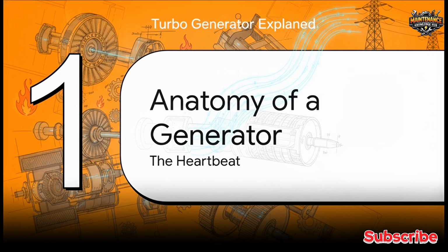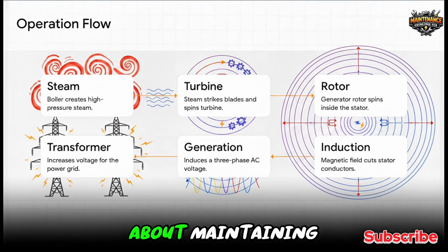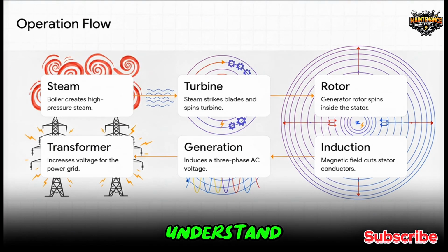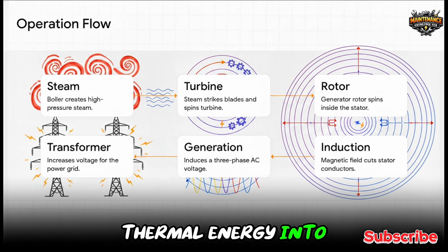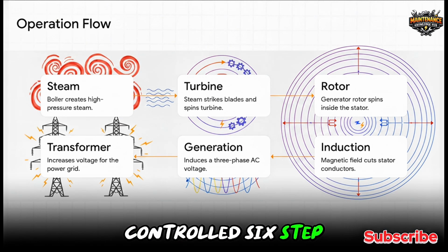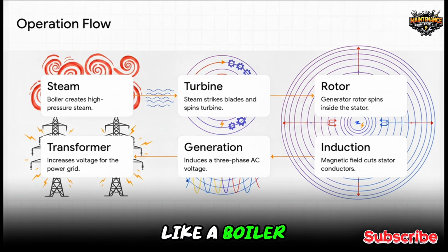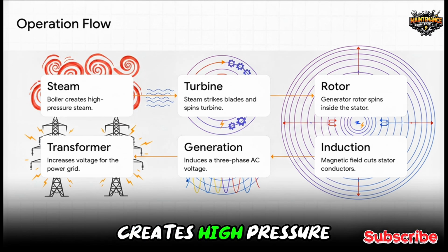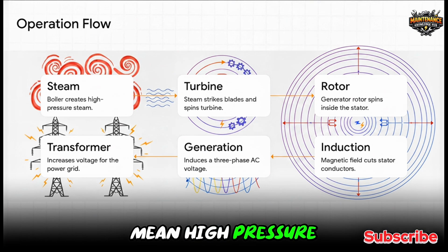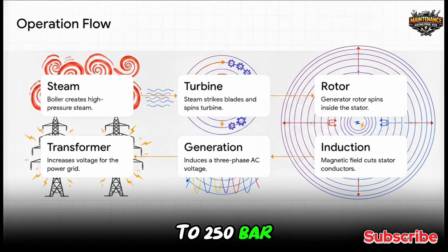The heartbeat. So before we can even think about maintaining this beast, we need to fully understand how it transforms thermal energy into electricity. The whole operation happens in a highly controlled 6-step flow. First up, a heat source, like a boiler or a nuclear reactor, creates high-pressure steam. And I mean high pressure. We're talking 150 to 250 bar at temperatures well over 500 degrees Celsius.